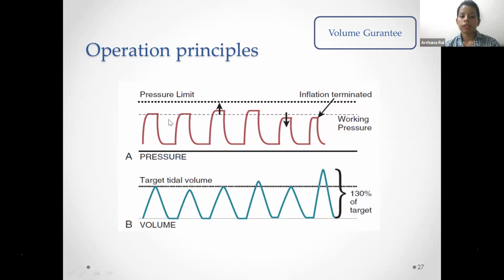So we have to keep seeing the working pressure. We have to keep a note of the working pressure and the pressure limit, so that the difference should not be more than 3 to 5 centimeters of water. Another safety mechanism in volume guarantee is that if the ventilator senses that the breath delivered has more than 130% of the tidal volume compared to what has been targeted, it will terminate the inflation.